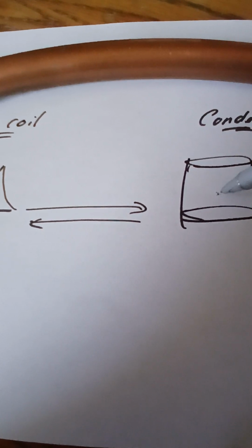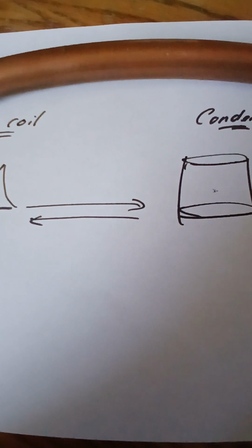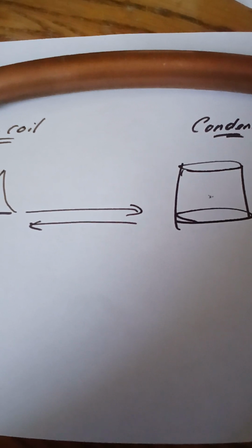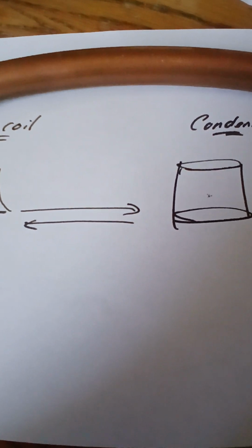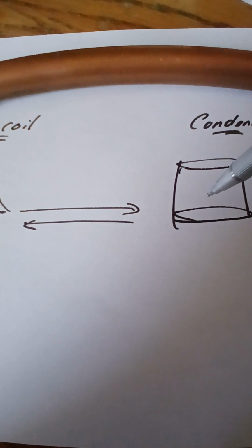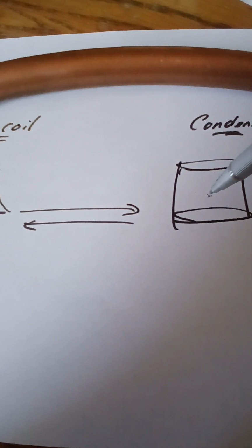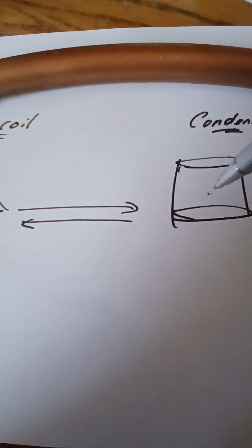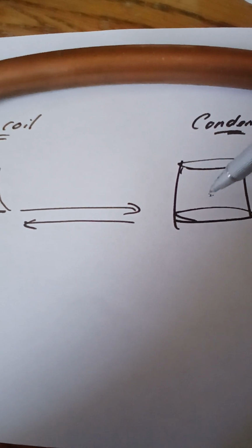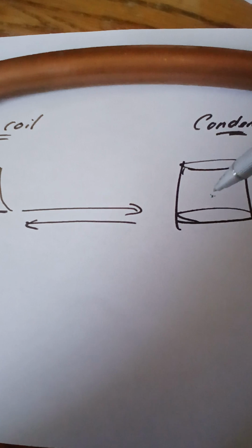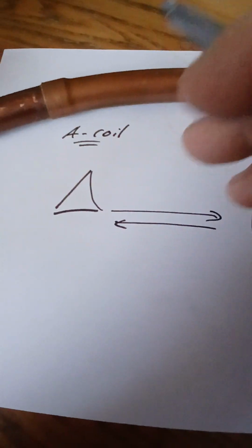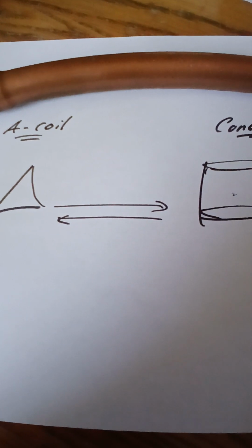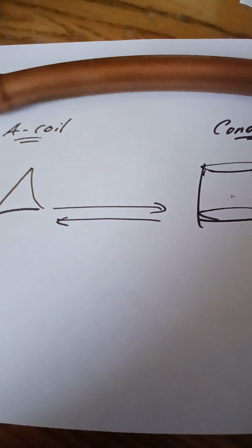If the system actually gets liquid in the compressor, it can actually slug the compressor and shorten the life expectancy, or perhaps worse, deep six the compressor. So the superheat and the subcooling need to be properly calibrated, and make sure no leaks are there.